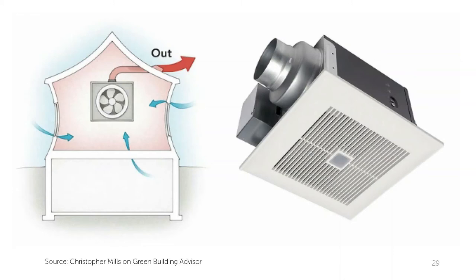There are three main types of mechanical ventilation: exhaust, supply, and balanced. Exhaust systems pull polluted air out of the home. Supply systems supply outside air into the home. Balanced systems exhaust and supply air. Exhaust systems are commonly located in bathrooms, over a stovetop in the kitchen, and in other areas of high pollutant generation, such as a dryer vent. Exhaust-only systems are allowed by code, but discouraged due to the heat loss. Additionally, the uncontrolled makeup air comes from unknown locations, like moldy basements or pest-ridden attics, without pre-filtering or conditioning, and gets distributed to unknown locations.